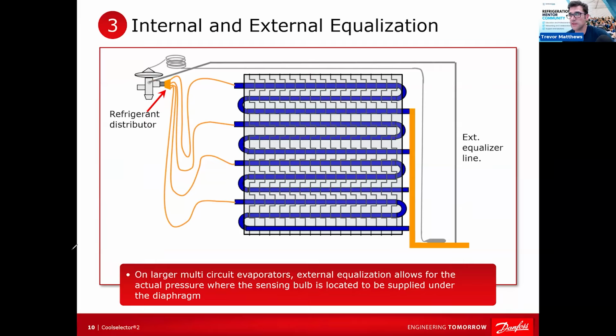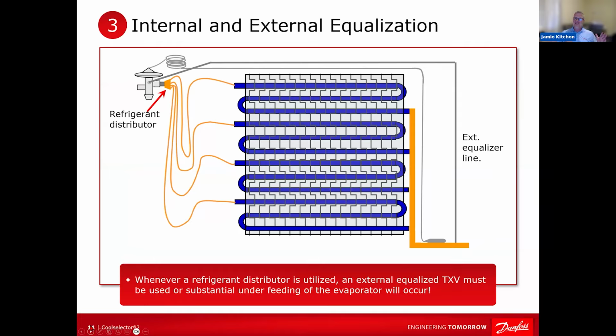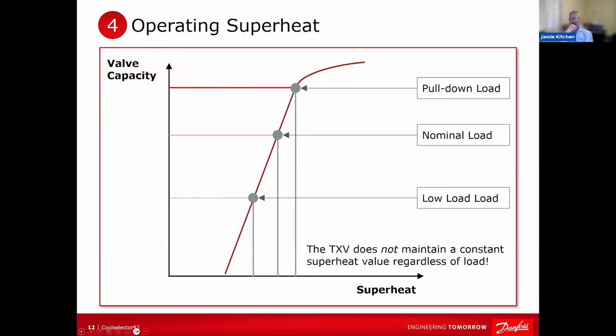Let's keep going. Now, on the bigger systems, you're never going to find an internal equalized. No. If you can show me an internal equalized 20-ton TXV, man, I'd be pretty impressed. So it's generally on the sub 3-4 ton kind of area. And definitely once you get below 1.5, 2 tons, you're going to start to see internal equalized valves.